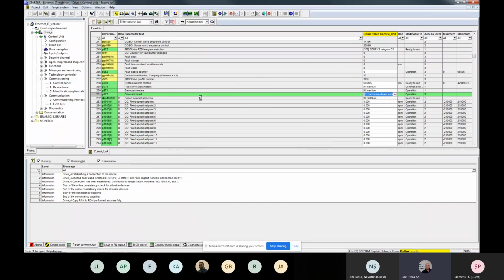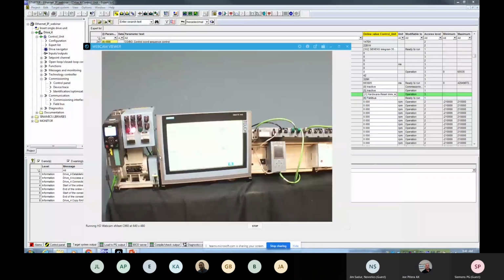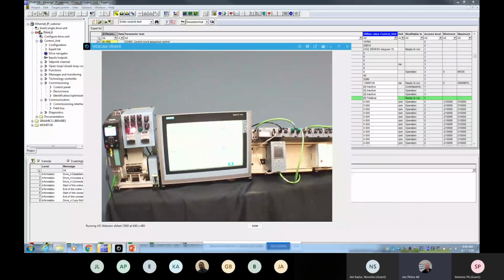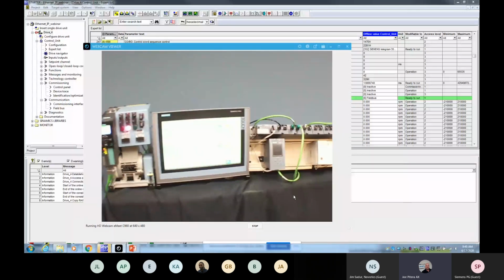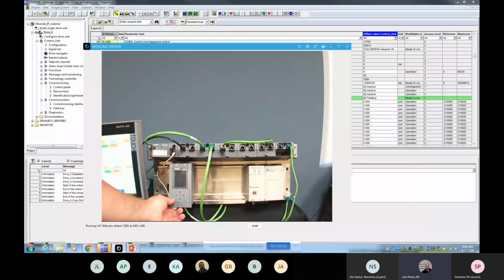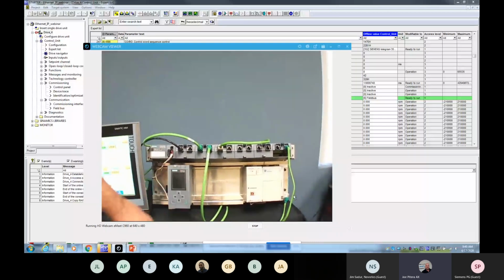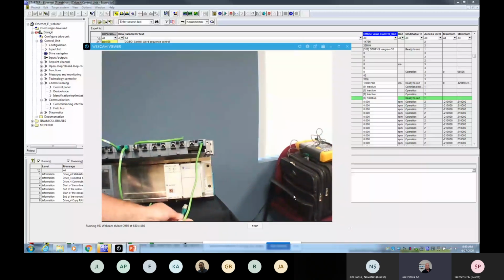Of course, you could go and disconnect the power on the whole drive cabinet, but if you have a bunch of drives and PLCs and other things, you may not want to cycle power that often. So as this thing is rebooting itself, we now have a fault on the communications on my drive. I am going to disconnect the Siemens PLC and connect the Rockwell PLC.